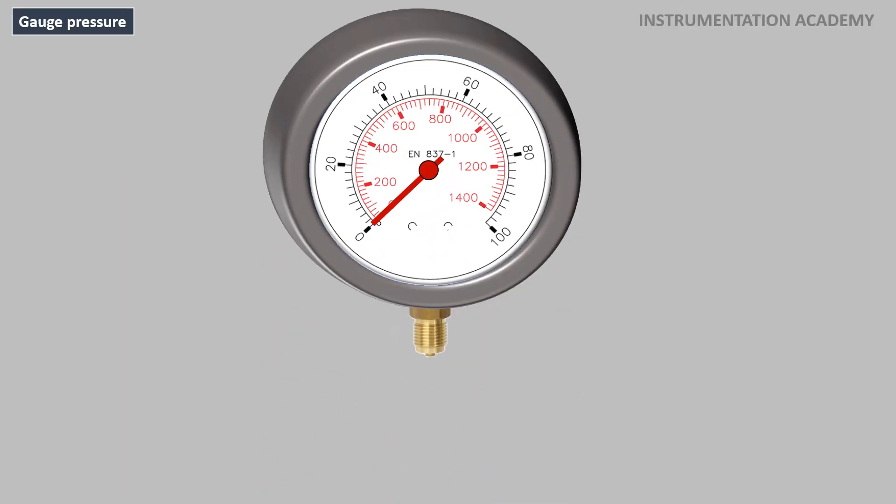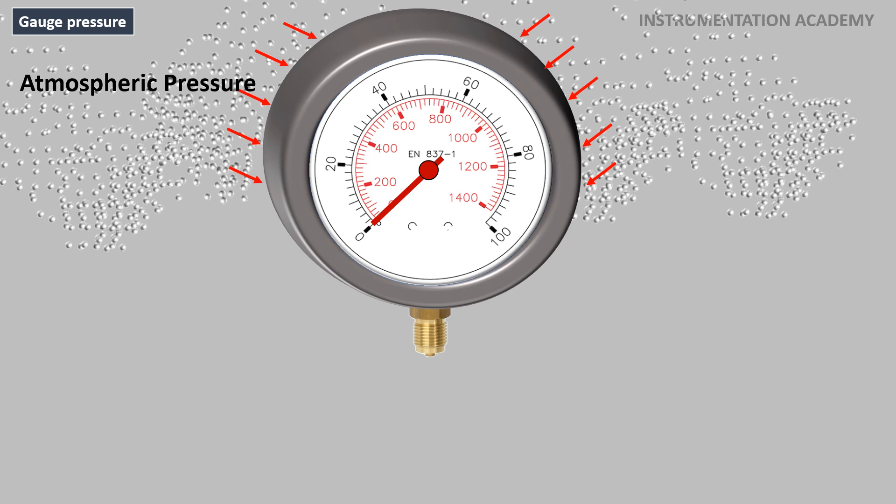Consider a normal pressure gauge. Before connecting the pressure gauge to any process, the reading in the gauge shows 0 psi. As we discussed earlier, every object on earth will undergo an atmospheric pressure. But that atmospheric pressure is not indicated in this gauge. That is because this pressure gauge is designed to indicate how much more the measured pressure is than the atmospheric pressure. That is here the atmospheric pressure is taken as the reference standard.